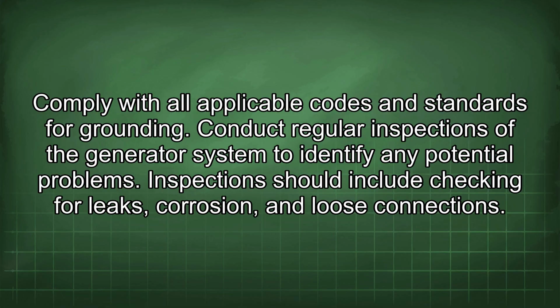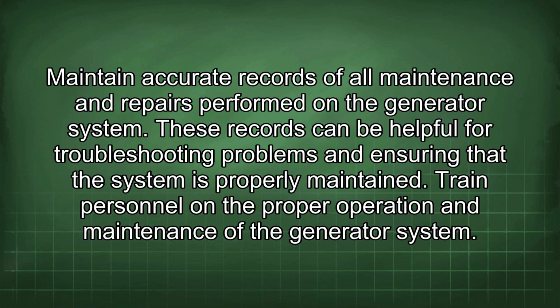Conduct regular inspections of the generator system to identify any potential problems. Inspections should include checking for leaks, corrosion, and loose connections. Maintain accurate records of all maintenance and repairs performed on the generator system. These records can be helpful for troubleshooting problems and ensuring that the system is properly maintained.